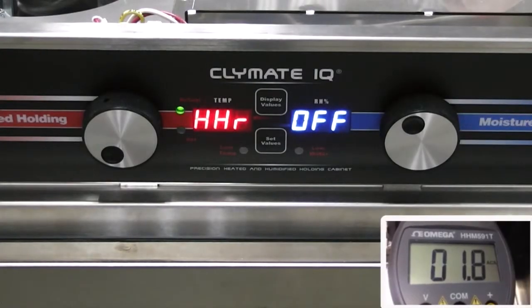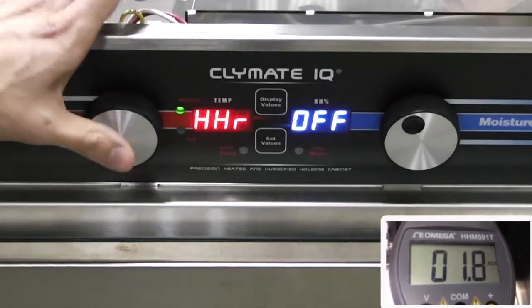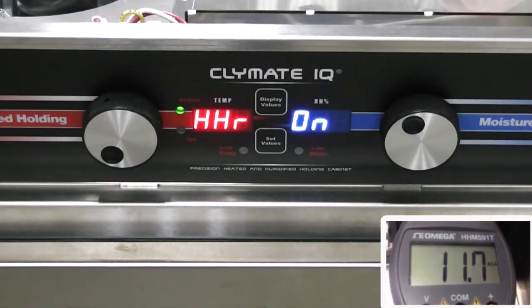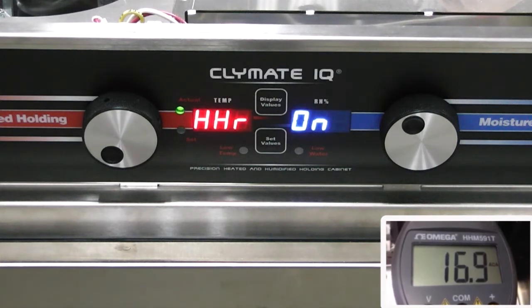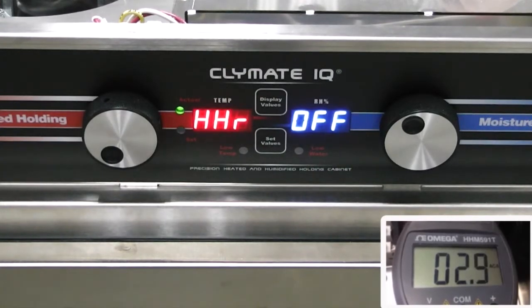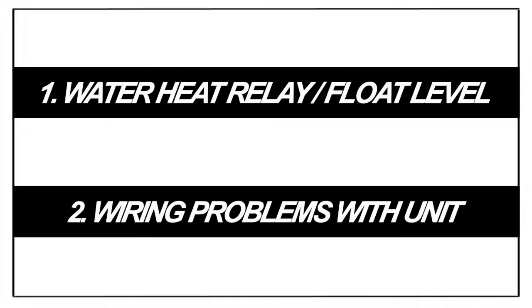Press the left encoder knob to turn the water heat relay on. The total amp seen should be approximately 16.7. As you can see, we got 16.9. Then you can turn the water heat relay off, and your only motor amp seen should be 2.1, and we read about 2.9. 2 important things to note.